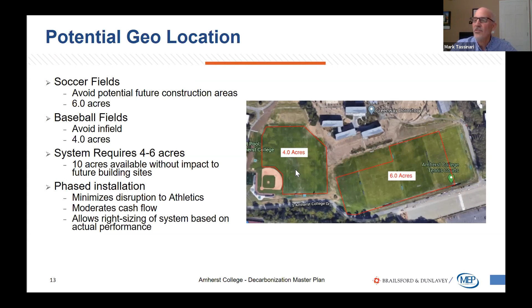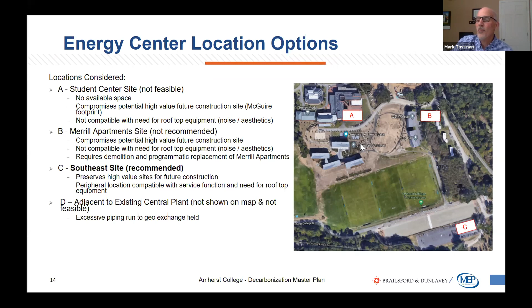The Energy Center will be a significant building housing the new heat pump plant. We struggled with various locations, looking at a few close to campus, but found those undesirable from a campus planning perspective. We're anticipating some rooftop equipment that will be loud, probably not ideal near academic and residential buildings. So we settled on a rough site at the perimeter of campus, which besides dealing with the noise factor, also preserves high-value sites for future academic or residential buildings.